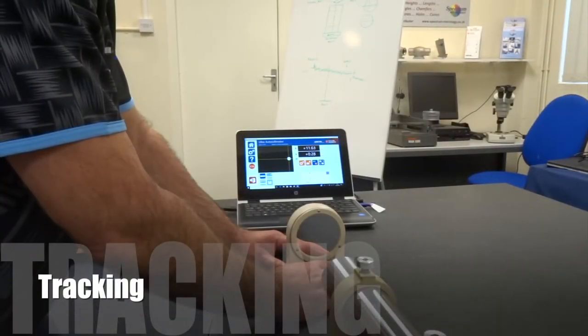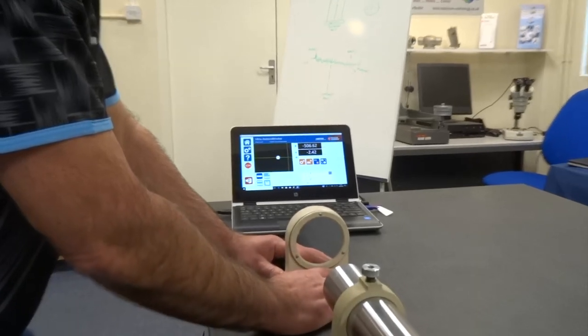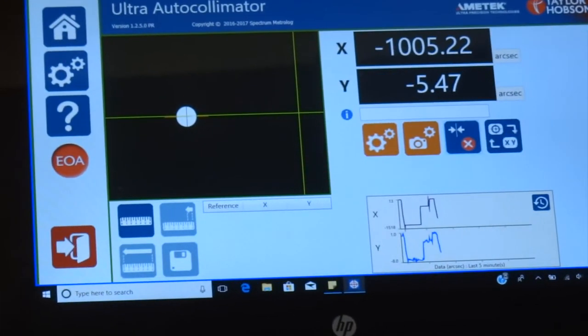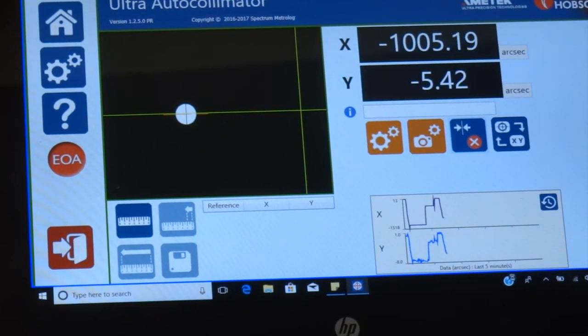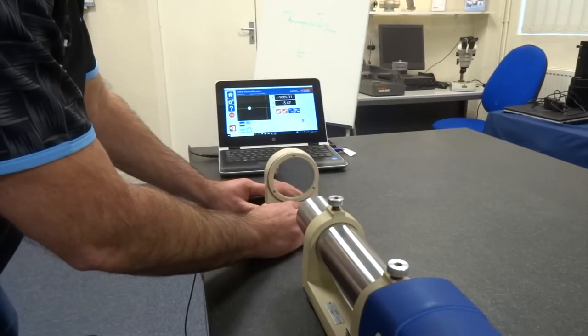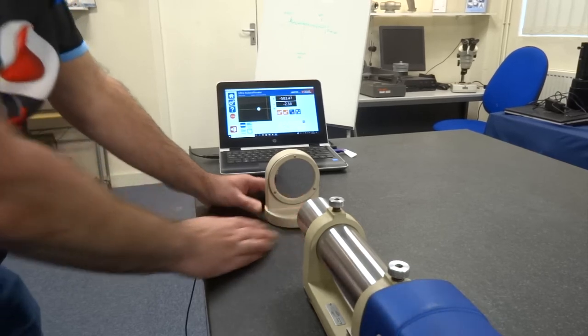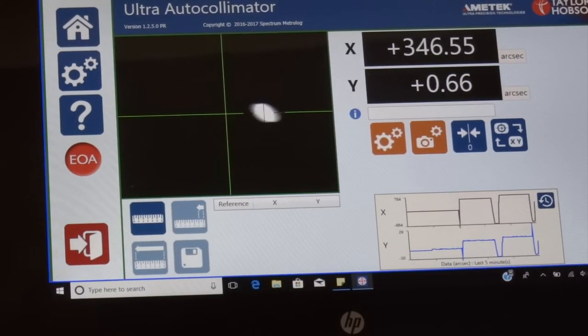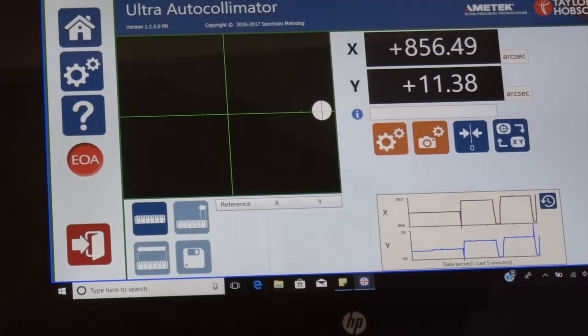Now we need to set the orientation and tracking. What we want to see is when the mirror tilts backwards and forwards, in other words going up and down, that the autocollimator is set so it also measures just up and down. How I normally do this is if I move the mirror, if I twist the mirror left to right, we should only have one axis on the autocollimator moving. The second axis should remain stationary.